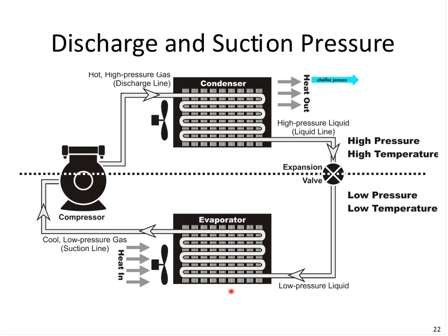There's two areas that we use for this temperature adjustment. So one would be the fan itself. So as we get down to the set point, we might slow this fan down, thus saving energy at the fan. And of course, any kilowatt hours expended on this fan motor ends up as heat in the refrigerated space.